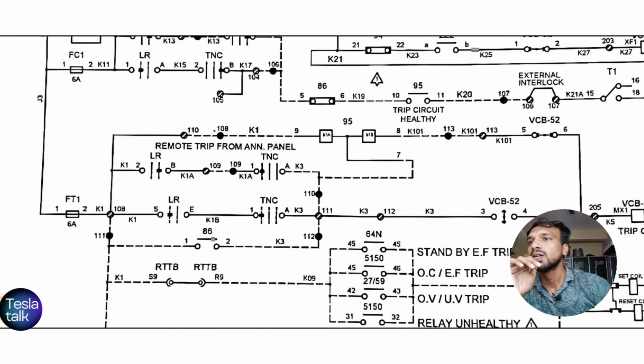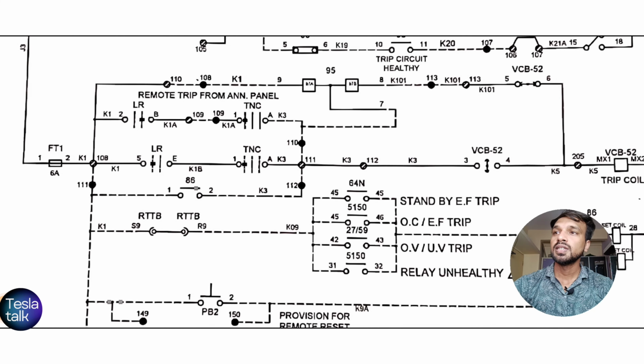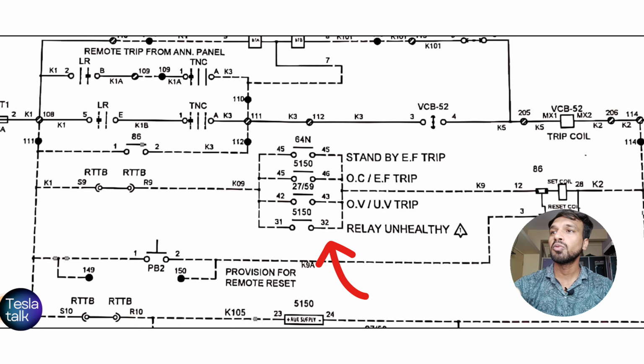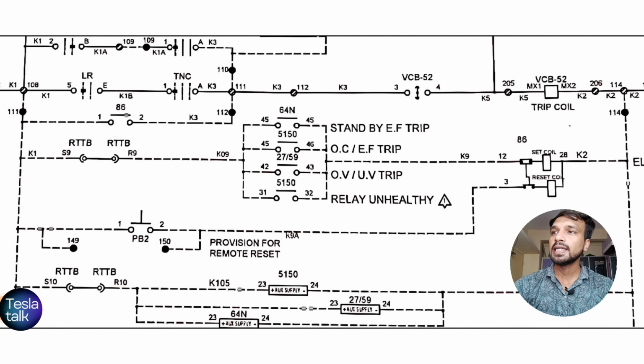There is also a trip circuit supervision relay. You can see here this one is the trip circuit supervision relay, which will monitor the healthy trip circuit. If the trip circuit fails, then it will generate an alarm. We will see the protection relays. Here are the protection relays. In this schematic, several protection relays are used to monitor the system and initiate the tripping command during faults.